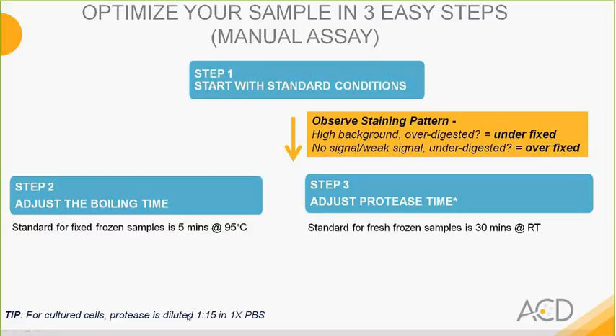Perhaps you are observing no signal or weak signal. Now, that could be related to the fact that the sample is underdigested, and that might be stemming from the fact that it was overfixed. Now, the ways to address those would be to adjust the boiling time, which is a target retrieval step. The standard for fixed frozen samples is 5 minutes at 95 degrees. You can also work by adjusting the protease time. And here I would like to mention that the standard for fresh frozen samples is 30 minutes at room temperature. Now, one other point for our customers who are using cultured adherent cells: the protease is to be diluted at 1:15 in 1x PBS.